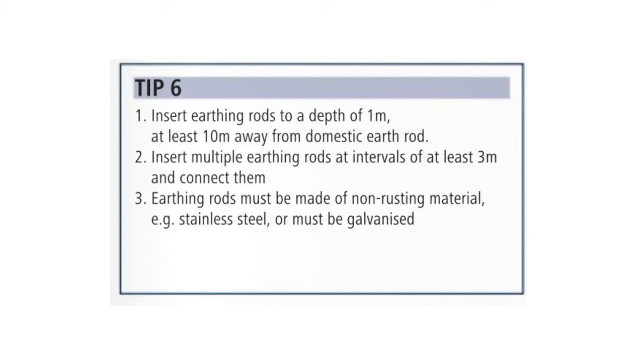So the earth rods must be made from non-rusting material. If you put just a steel earth in and it rusts, the rust acts as an insulator and it stops the fence going to ground well enough. Really, a galvanized thing is the right answer. If we painted it, now you could probably get away with painting an earth rod with a red oxide paint that is a conductor. But if you paint it with a regular paint, it's again going to be an insulator. So a galvanized rod is really what we want to be using.